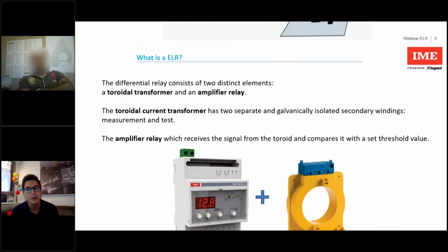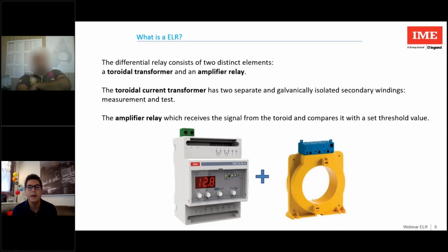What is it made of? In the industrial field, the ELR consists of two devices, a toroid and a relay. The toroid has the task of detecting the current and returning it to the relay. At the relay, you can set a differential current threshold, and if it is reached, it trips.